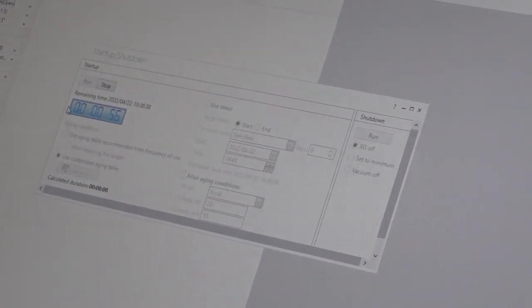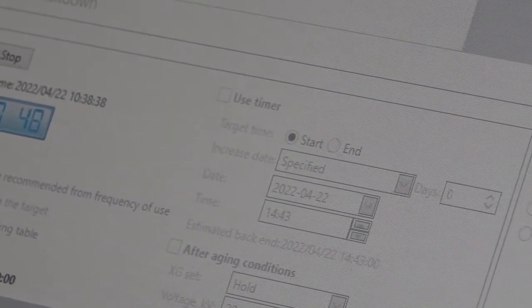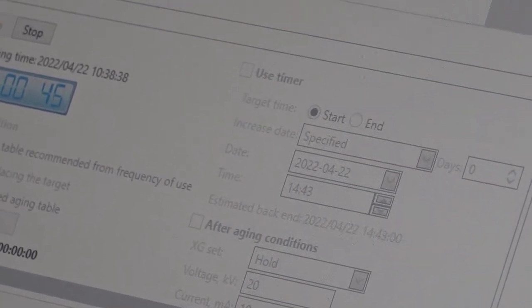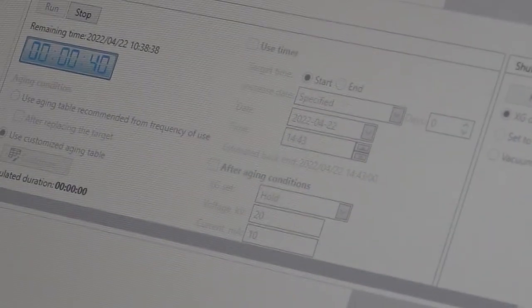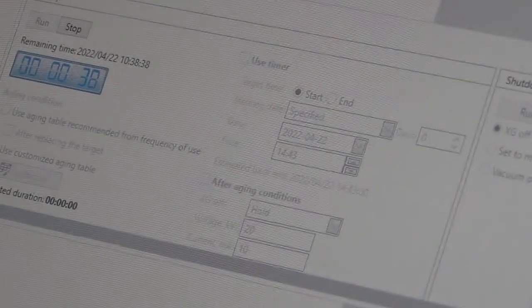When the software was opening, there was a message saying it cannot load because the license is not there. What was that? At the beginning, if the communication is not there, that time only it will come like that. Two or three messages came saying this feature is not there because there is no license. This software is common for all the XRDs, even the floor model can use the same software. But only what is required for this model is enabled in that software. The remaining things they locked.